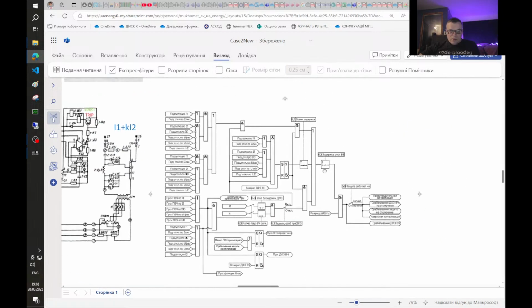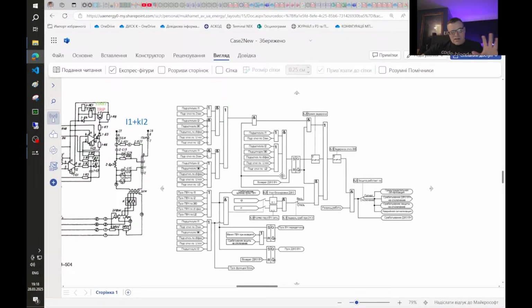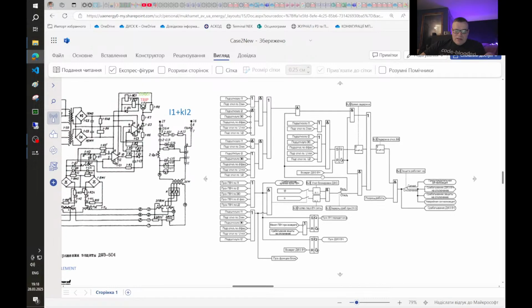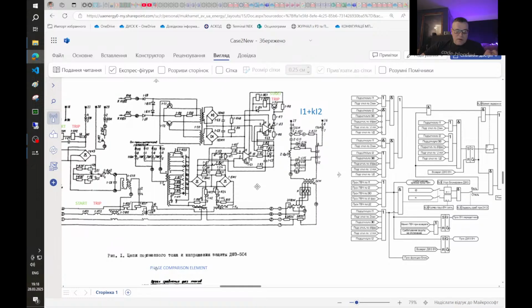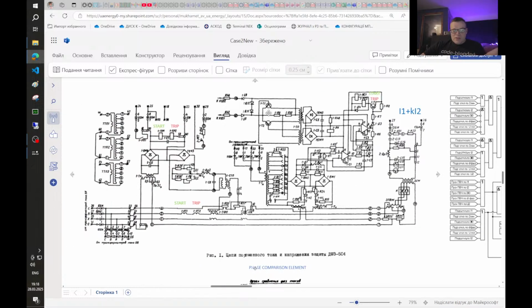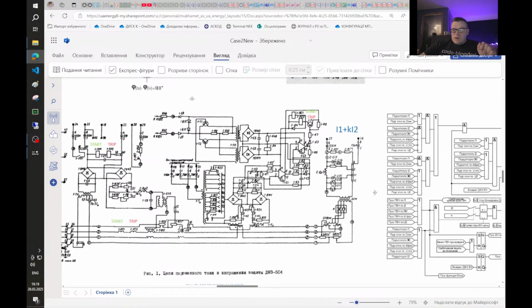If you look at the tripping logic, it looks complicated, and it's really more simple, and I want to describe how protection works on the old electromechanical scheme. It looks a little bit complicated, but I believe it is easier to understand how it works. This part of the scheme is distance relays. These two relays are related to phase current, and these two relays you can receive a combination of zero sequence current and negative sequence current.